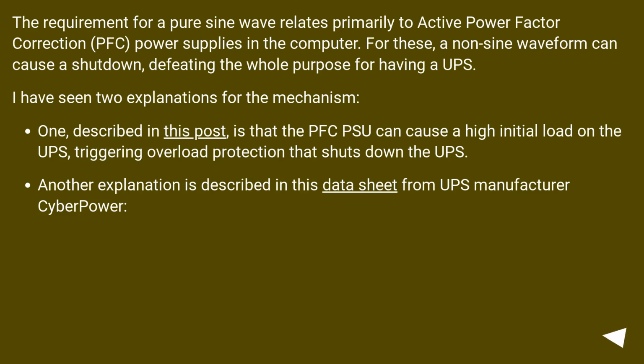The requirement for a pure sine wave relates primarily to active power factor correction, PFC, power supplies in the computer. For these, a non-sine waveform can cause a shutdown, defeating the whole purpose of having a UPS. I've seen 2 explanations for the mechanism. One, described in this post, is that the PFC can cause a high initial load on the UPS, triggering overload protection that shuts down the UPS.